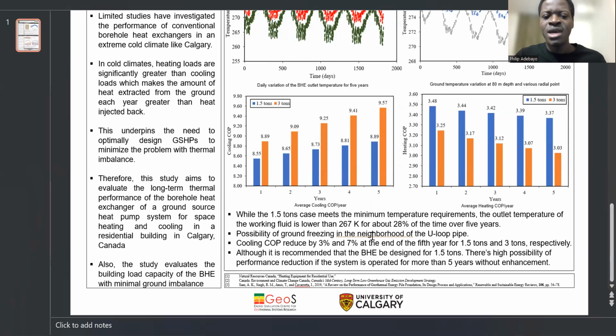So in conclusion, while the 1.5 tons case meets the minimum temperature requirement, the outlet temperature of the working fluid is lower than 267 Kelvin for about 28% of the time over the 5-year storage period for the 3 tons case. As you can see from the ground temperature distribution, there is a high possibility of ground freezing in the neighborhood of the U-loop pipe or the ground bore heat exchanger itself, especially for 3 tons and even for 1.5 tons if we continue to use it for more than 5 years. There's a high possibility of ground freezing around the bore heat exchanger. So the cooling COP reduced by 3% and 7% at the end of the 5th year for 1.5 tons and 3 tons, respectively.